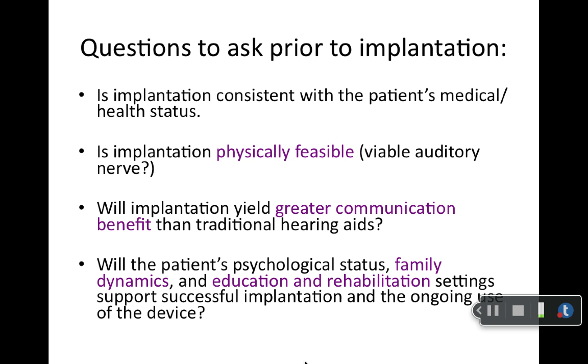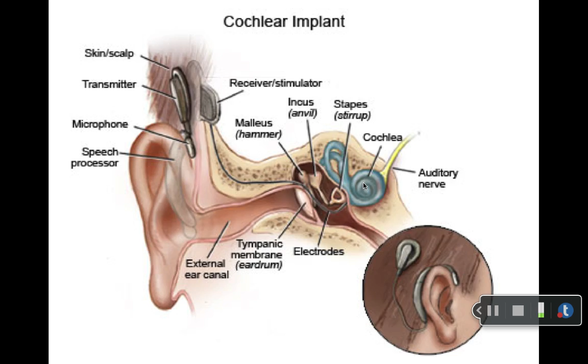So here we have external processes and internal processes. Over here is the microphone. It picks up the sounds. It gets coded in the speech processor. Electrically, it gets sent through the transmitter, through a radio wave to the receiver stimulator, down through the middle ear. The middle ear has nothing to do with it anymore. There's an electrode array inserted into the cochlea. The electrode array electrically stimulates the auditory nerve.